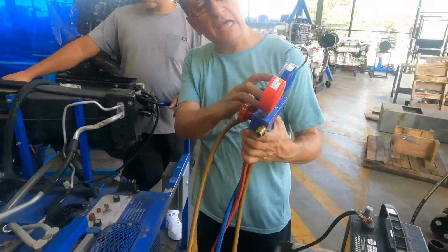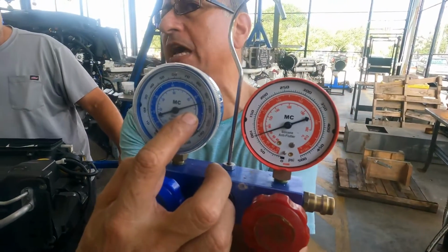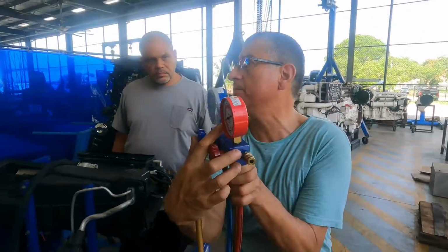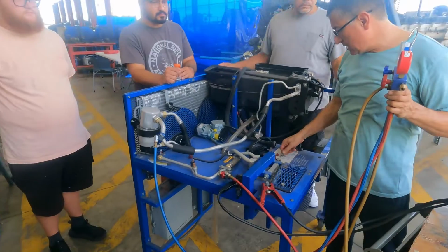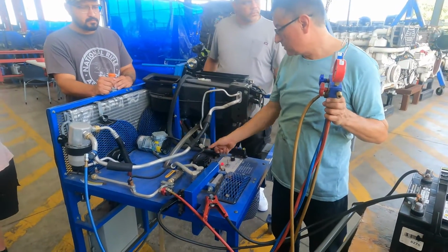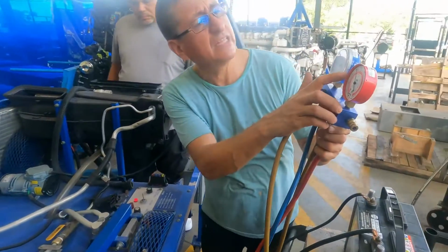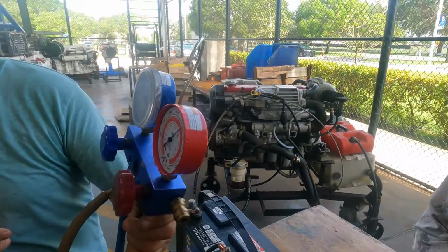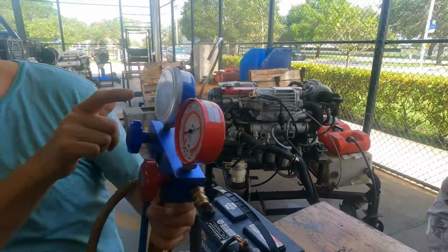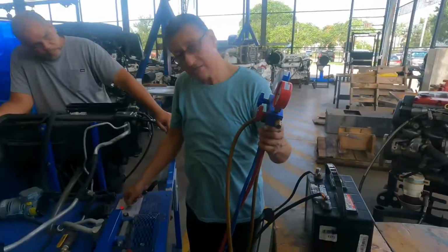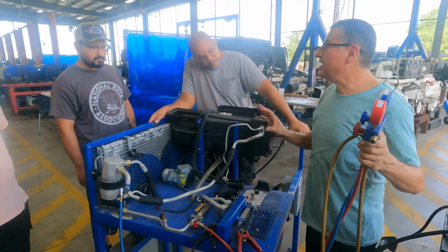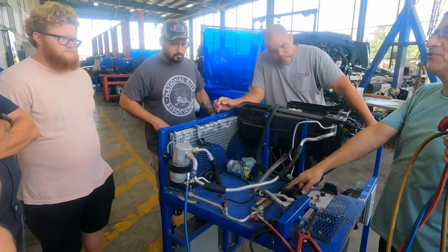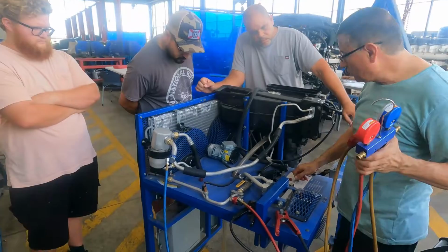Look, I have 95 psi in the low pressure side, and I have around 100 in high pressure. You see? Okay, we are going to start the system. Look at this. The pressure is 220, 250, 300. That's too much. And here 90, 350. Something is wrong, and the pressure goes up. You see? That's why the pressure relief valve was activated.